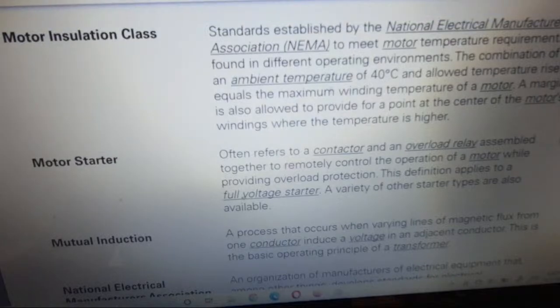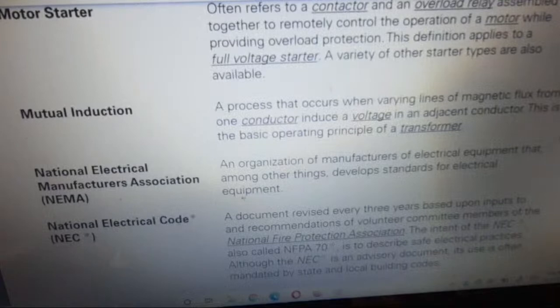Motor starter often refers to a contactor and an overload relay assembled together to remotely control the operation of a motor while providing overload protection. This definition applies to the full voltage starter. A variety of other starter types are also available. Mutual induction: a process that occurs when varying lines of magnetic flux from one conductor induce a voltage in an adjacent conductor. This is the basic operating principle of a transformer.